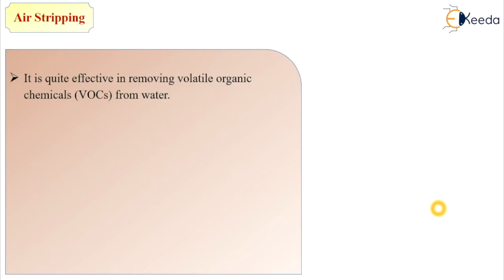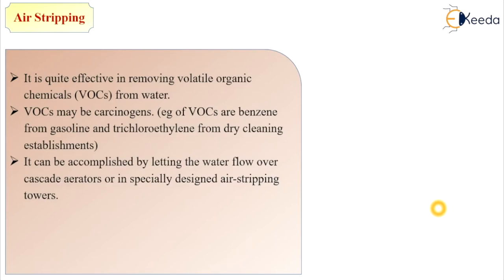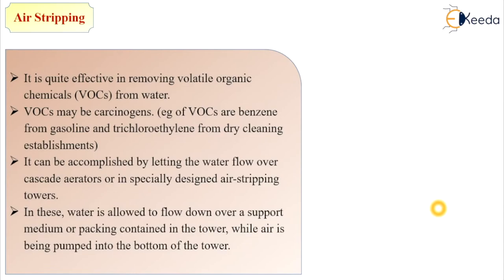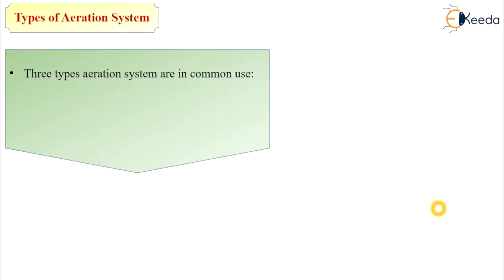Under spray aerators, subtypes include aeration by nozzle and air stripping. Air stripping is quite effective in removing volatile organic chemicals present in water. Volatile organic chemicals may be carcinogenic — for example, VOCs such as benzene from gasoline and trichloroethylene from dry cleaning establishments. This can be accomplished by letting water flow over a cascade aerator or in specially designed air stripping towers, where water falls over a support medium while air is pumped into the bottom of the tower.